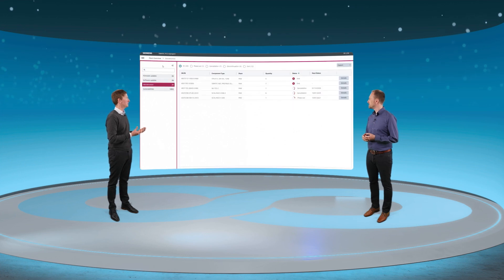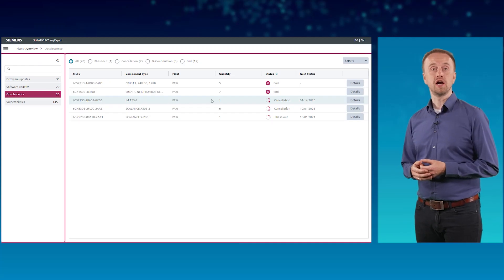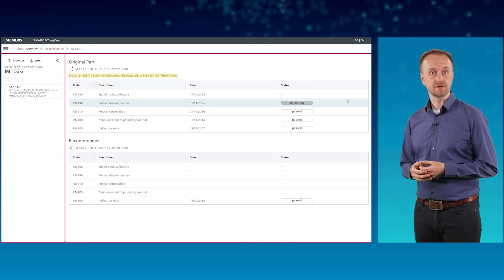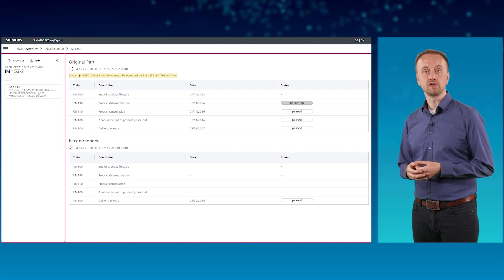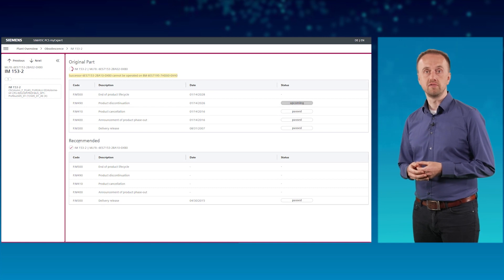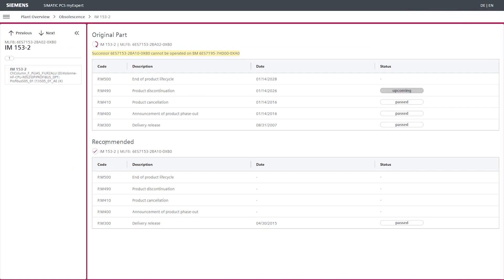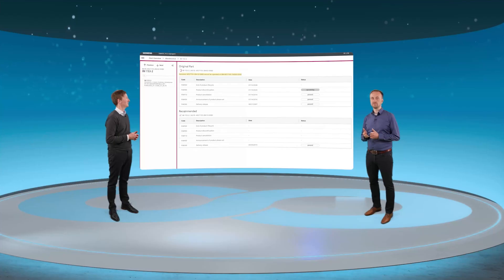Let me show you how obsolescence can be tracked within SIMATIC PCS My Expert. The product IM153-2 with its MLFB is used once at indicated locations in this demo system. The current lifecycle status PM410 product deletion has been reached and the next milestone, product discontinuation, is upcoming in 2026. A note: successor can only be operated on a certain bus module, which provides additional insights. By processing this information and taking early actions before a part is only available as a repair service or even no longer available, you can save costs and increase the availability of your plant.